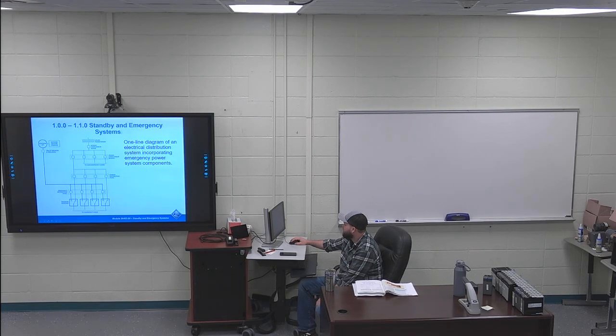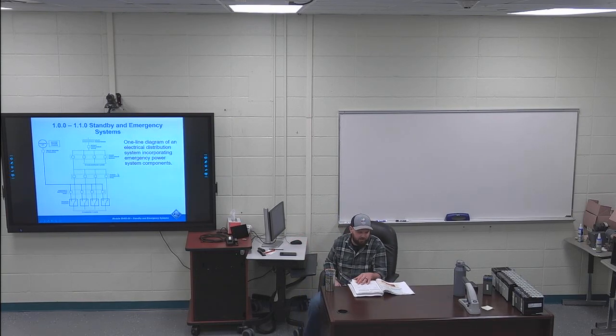So power gets shut off by the utility. In our area, when something happens, Entergy shuts off power. This generator set has to come back on within 10 seconds, and then powers up everything that has to be on the emergency side. So you can see your transfer switches right here, with the line coming down from your normal distribution panel. The transfer switch is just going to switch from normal power to emergency power. It's just a simple one-line diagram of an emergency set.